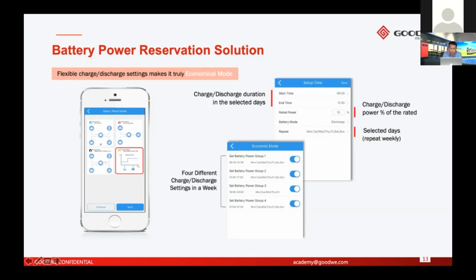For example, here I can choose Monday and Tuesday, and I follow this logic: I want to charge the battery on Monday and Tuesday from 8 o'clock to 10 o'clock. And from maybe Friday to Saturday, I want to discharge the battery from 8 o'clock. You can set different charge and discharge logics in different groups, and these four groups are separate, independent logic. You can set the charge or discharge time, and the power: the max charge power for the battery during the charge time, and the max discharge power from the battery during the discharge time.